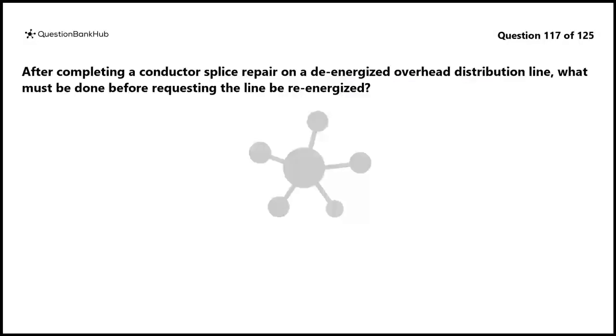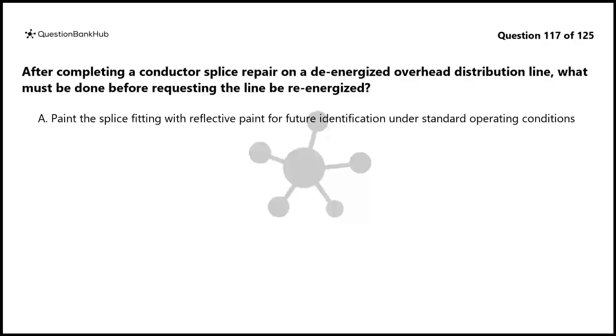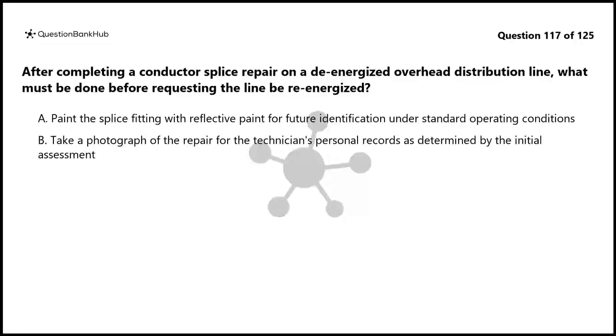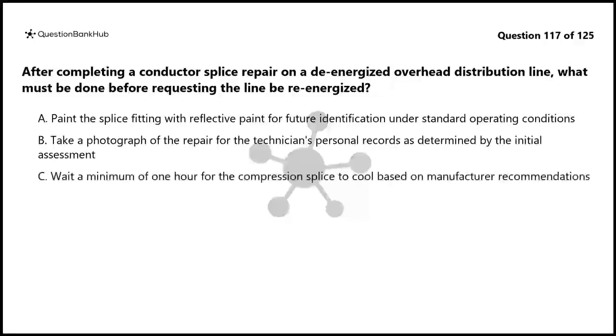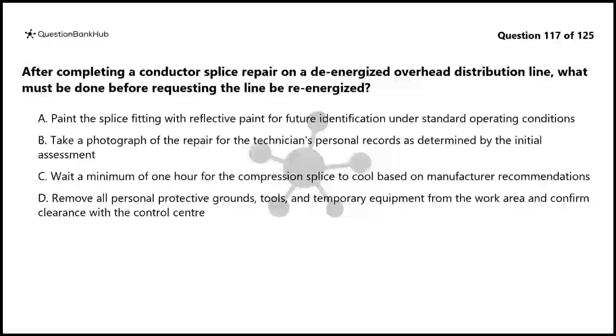Question 117. After completing a conductor splice repair on a de-energized overhead distribution line, what must be done before requesting the line be re-energized? A. Paint the splice fitting with reflective paint for future identification under standard operating conditions. B. Take a photograph of the repair for the technician's personal records as determined by the initial assessment. C. Wait a minimum of 1 hour for the compression splice to cool based on manufacturer recommendations. D. Remove all personal protective grounds, tools, and temporary equipment from the work area and confirm clearance with the control center.